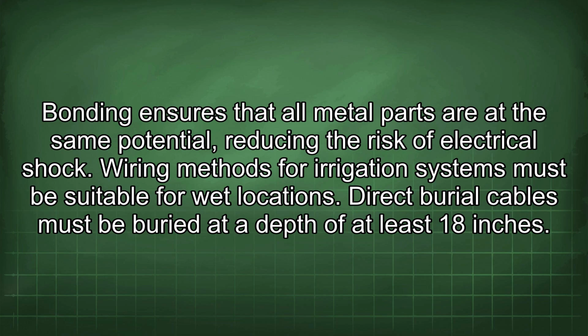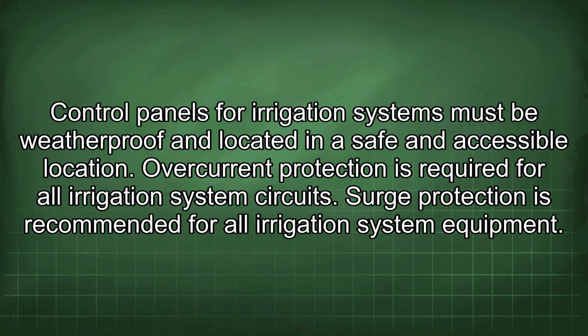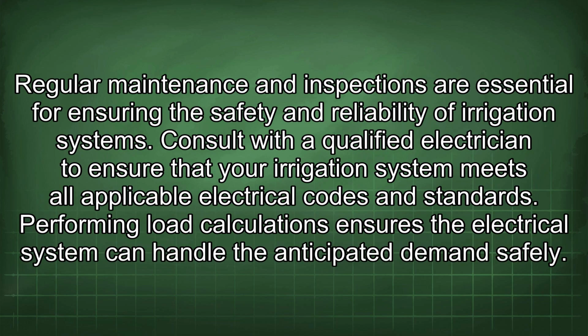Wiring methods for irrigation systems must be suitable for wet locations. Direct burial cables must be buried at a depth of at least 18 inches. Control panels for irrigation systems must be weatherproof and located in a safe and accessible location. Overcurrent protection is required for all irrigation system circuits. Surge protection is recommended for all irrigation system equipment. Regular maintenance and inspections are essential for ensuring the safety and reliability of irrigation systems. Consult with a qualified electrician to ensure that your irrigation system meets all applicable electrical codes and standards.